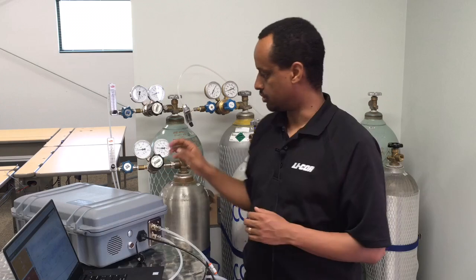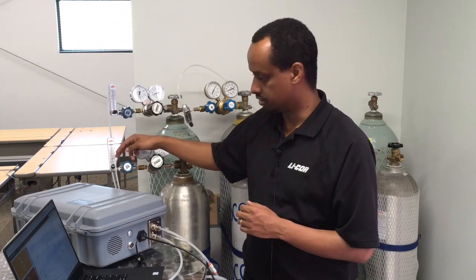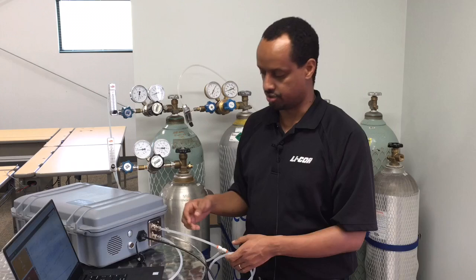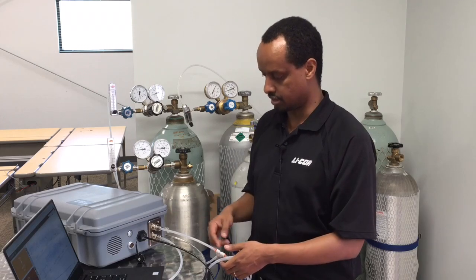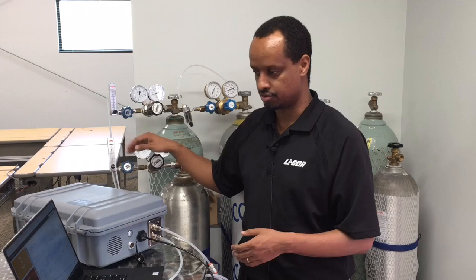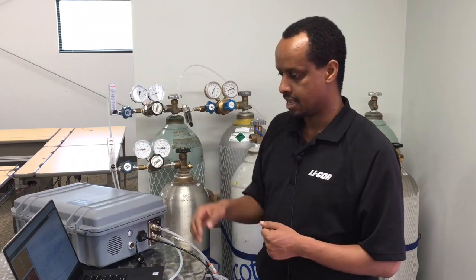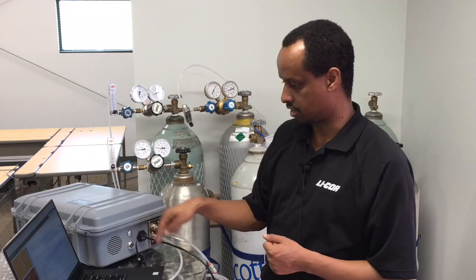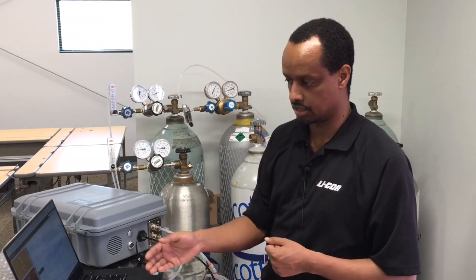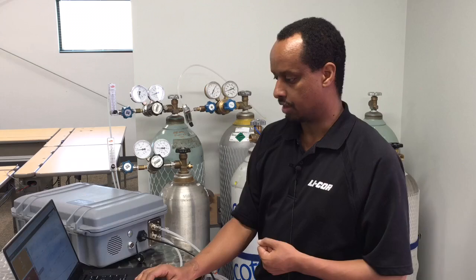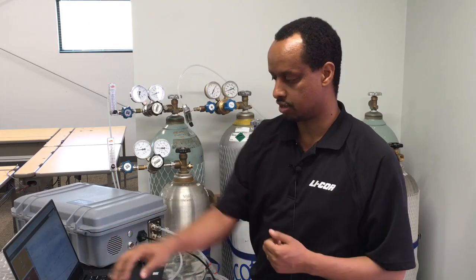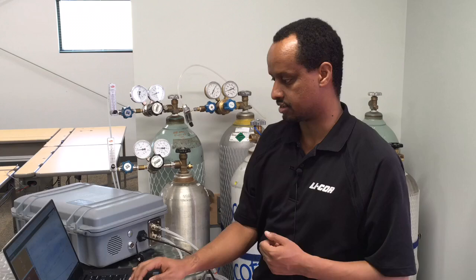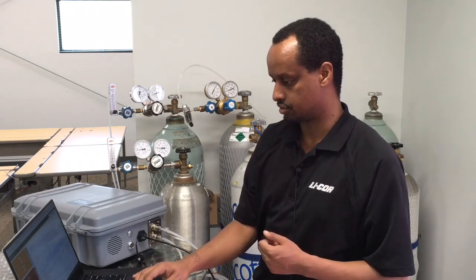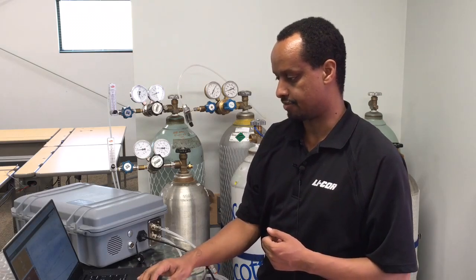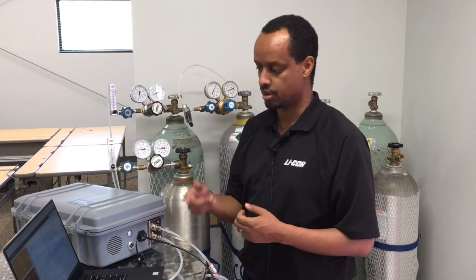So I've already started flowing the gas, as I said, at near 1 liter a minute. The instrument takes about 0.3 liters per minute, and so the excess is flowing out. You can adjust that to about half a liter or 0.6 liters per minute. And we're looking at the software. We're connected here through the Ethernet cable, and we're monitoring the gas concentration. So for zero, if you look here on the software, you can see that the methane readings are relatively stabilized, as well as the CO2, but however the water readings are still falling, and this is why it's going to take a while for doing the zero.